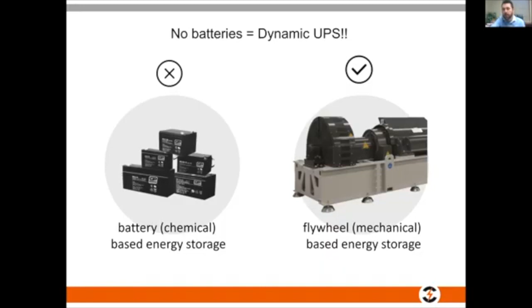We're going to get rid of the batteries and move over to the flywheel, storing energy mechanically. This is the new one-line diagram. The first thing you'll note is the electrical infrastructure as it pertains to the switchgear hasn't changed. I still have an input breaker, an output breaker, and a bypass breaker, absolutely no different. The only change in the infrastructure away from the switchgear is the ATS.